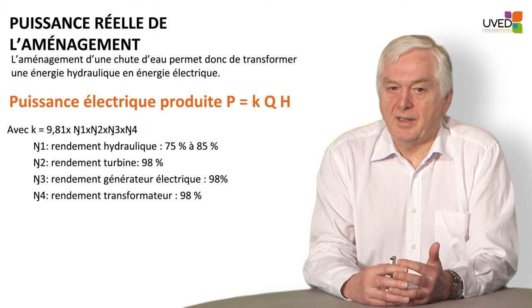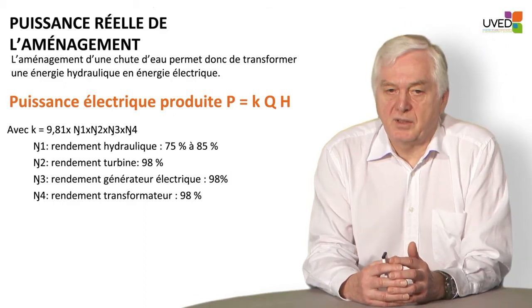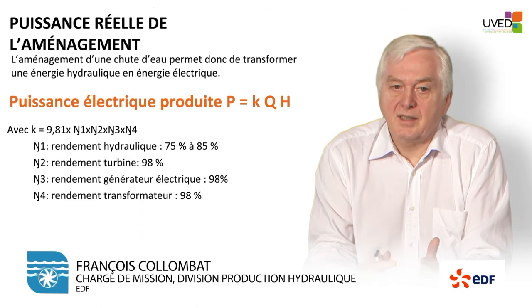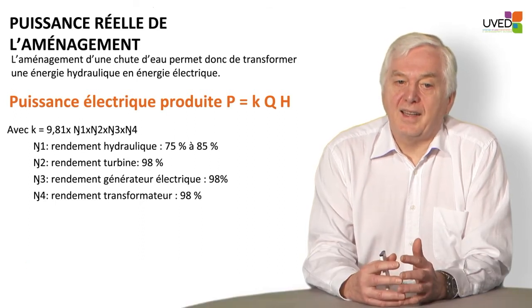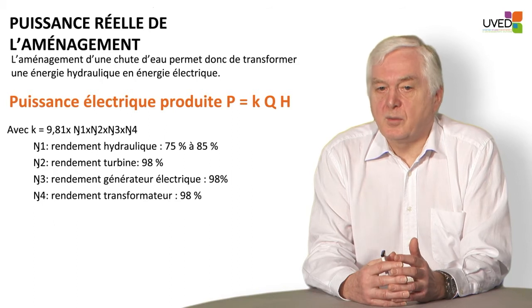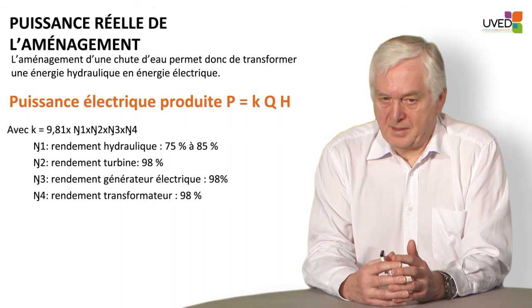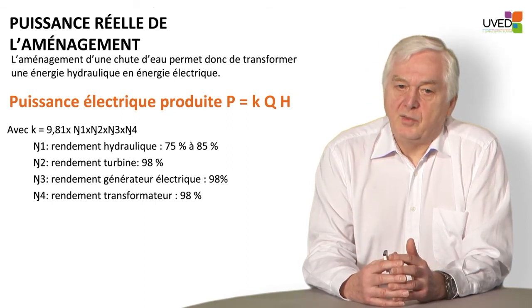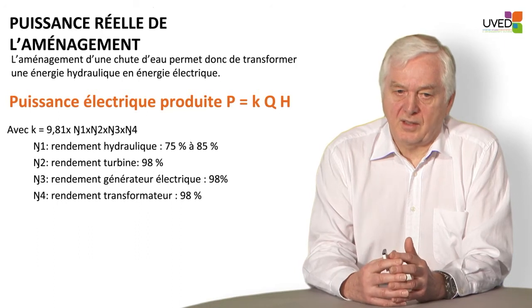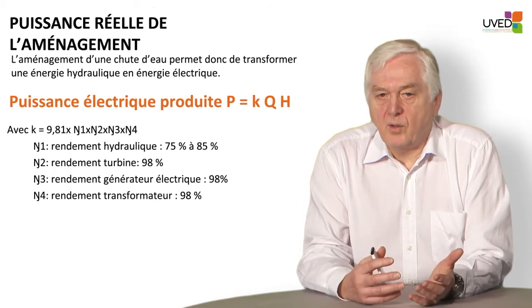When water reaches the turbine, the hydraulic power is turned into mechanical power, and yield is quite high — up to 98% turbine yield nowadays. The mechanical power then drives an electric generator, producing electrical power, also at 98% yield. Most of the time, the voltage generated by the alternators is relatively low, and before we can inject it into the grid, we need to increase it with an electrical transformer. Transformers also have a very high yield of 98%.